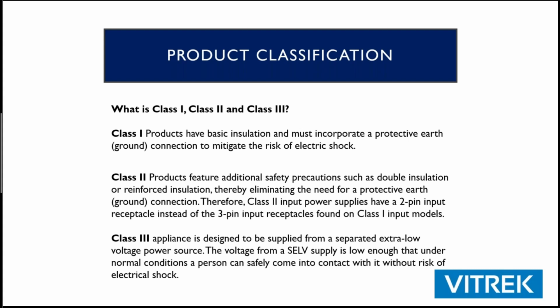Class 3 is something that we don't really get involved in testing very often because it kind of falls under the testing guidelines. Typically, your skin's going to insulate up to about 30 volts. Products are less than that, and they have a limited power supply. They're pretty much deemed safe. And you're not going to see them tested at a production level very often with a HIPOT tester, although at the sub-assembly level, it's quite common.